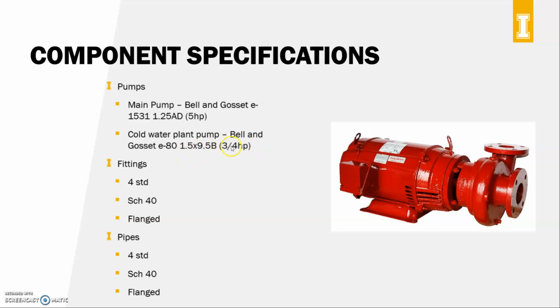1.5x9.5B 3/4 horsepower pump. Now, unfortunately, because there's so much head required in our system, around 130 feet for the main line, we had to choose a pump that's not really operating at the most optimal efficiency. Unfortunately, it's only operating at about 50% efficiency. I'll talk a little bit more about that when I get to the system curve. However, since there's less head required, we were able to operate at a higher efficiency on our cold water pump.